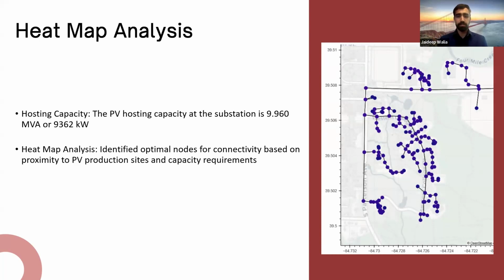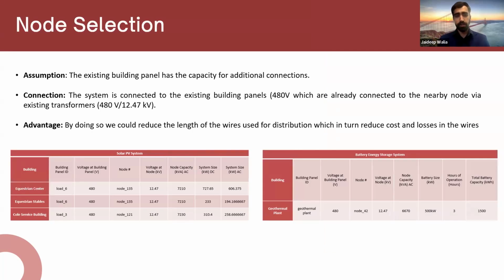Based on the heat maps, we identified nodes to connect the PV system as well as the battery system, assuming the existing panels already have connection points. We would connect our PV systems directly to the building panels, reducing the need for additional interconnection costs and transformers, since the heat map confirmed transformers already exist with 480 volt to 12.47 kilovolt transmission values.